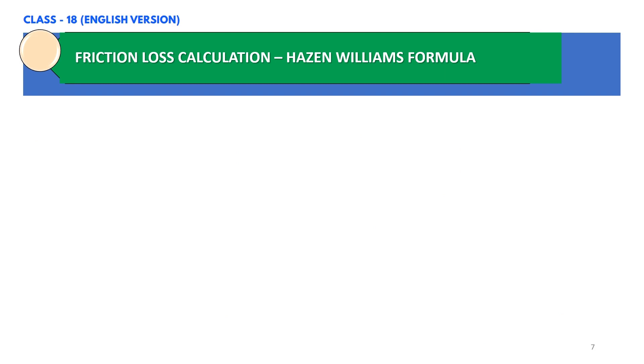In this slide let's have a look at a friction loss calculator based on the Hazen-Williams formula. This calculator is available online from the link shown in this slide. You can enter your data, and if you have fittings such as 90-degree elbows, you just type the fitting type and quantity. For a 3-inch pipe the calculator gives a friction loss result of 2.8 PSI.